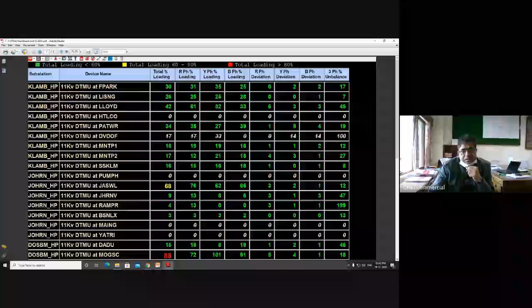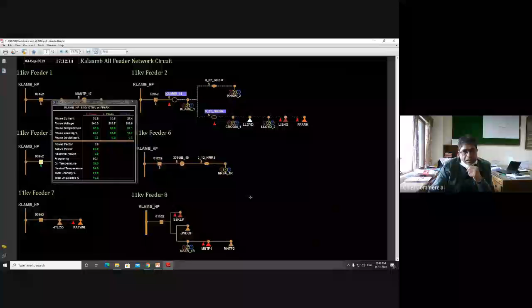Then there is the DTMU, the distribution transformer monitoring unit, which measures winding temperature, oil temperature, and oil level. This DTMU screen looks like this. It shows the loading per phase, and this shows the deviations. Unbalance is also shown, and these are the feeders. We have installed various equipment, auto reclosers and sectionalizers, and it is showing the status of these DTRs also in this diagram. So it is coming live through communications.